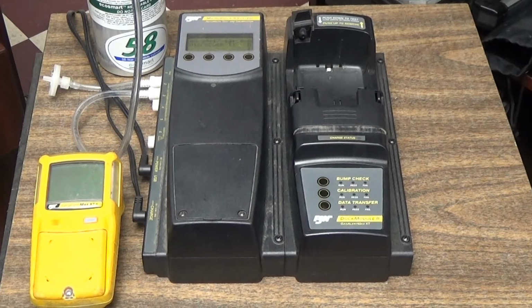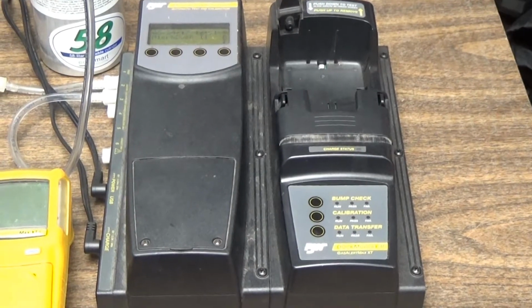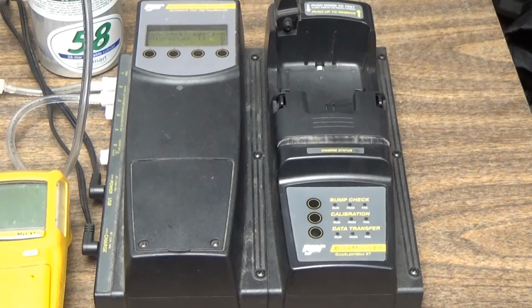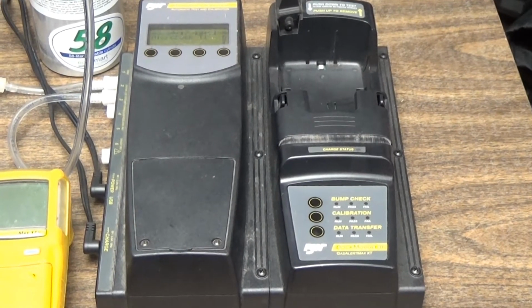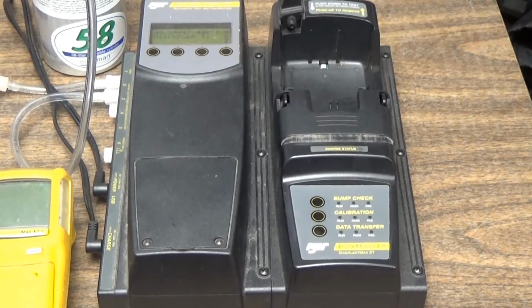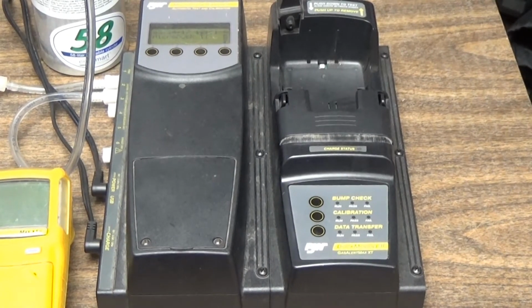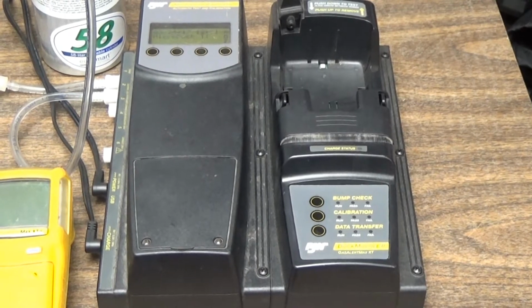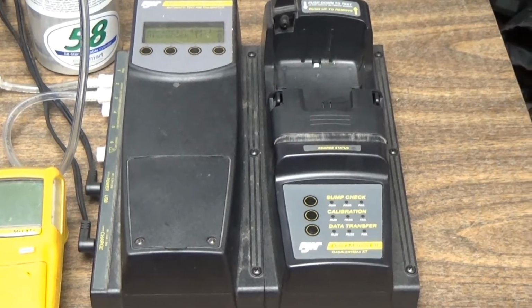Hello everyone. Today we'll be taking a look at the BW Gas Alert Max 2 4-gas meter. We'll be covering how to bump and calibrate it and some of the current problems that we've been having with the meters. Here we have a standard bump station that most control rooms have. Most of these bump stations have 2 to 4 bays in it. When you're bumping or calibrating the meter, you should always use this bump station.